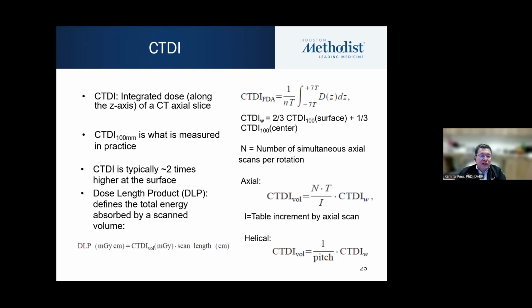We have also the patient dose, which typically is measured through CTDI, which is an integrated dose along the Z-axis. In practice, 100 millimeters is what is measured. CTDI is typically 2 times higher at the surface than it is at the center. And we have other parameters that are indicators of dose delivered to the patient, typically the dose length product, which are defined here. Again, CTDI is often defined using those integrations over a scan, and they are a little different for axial and for helical scans.